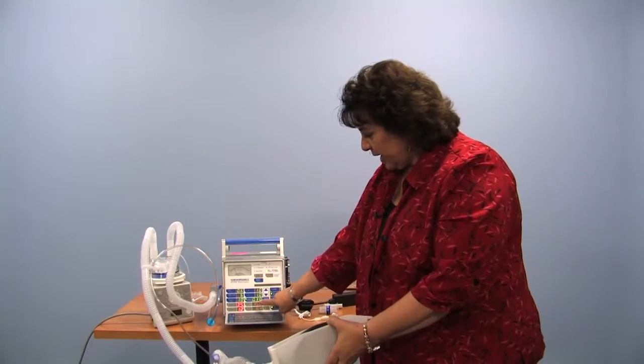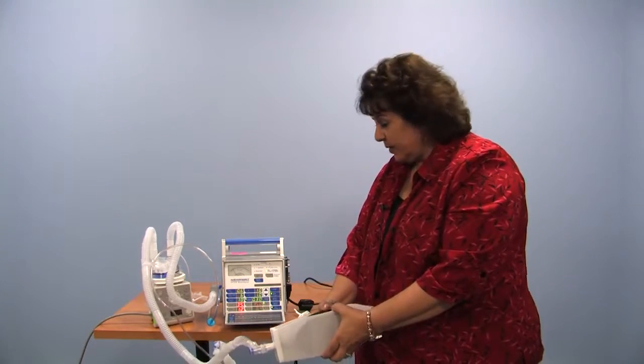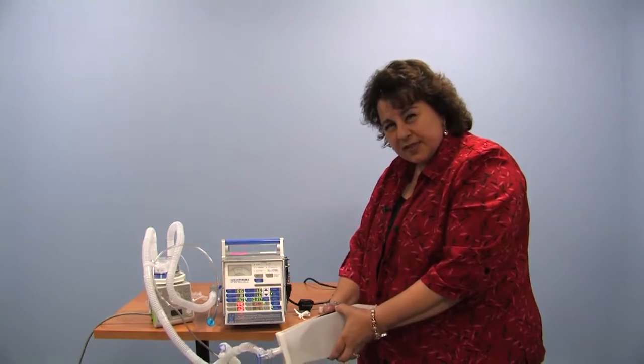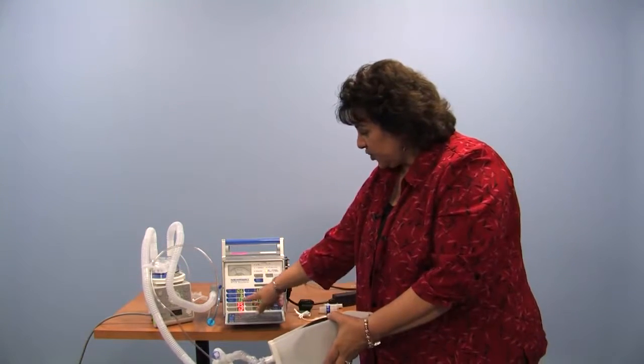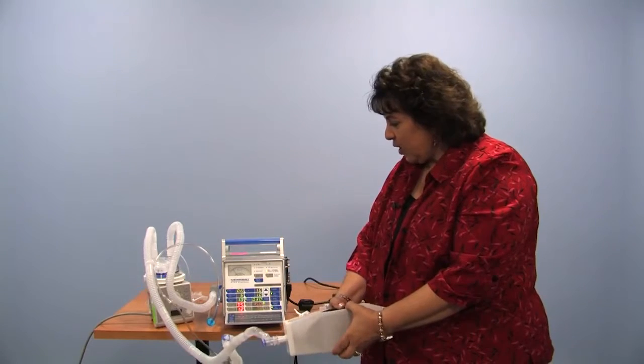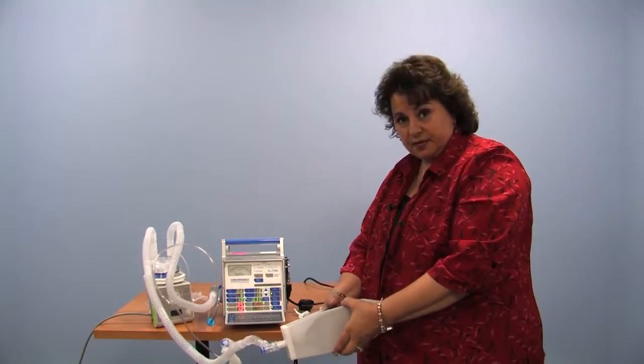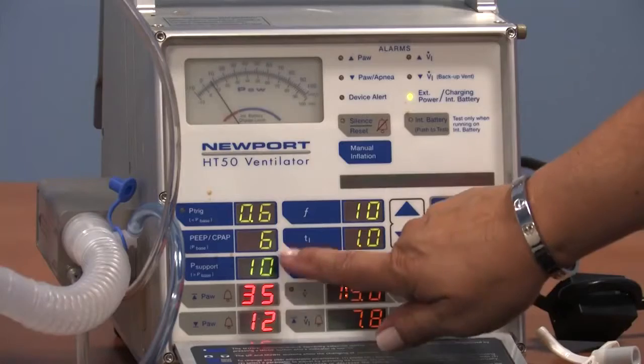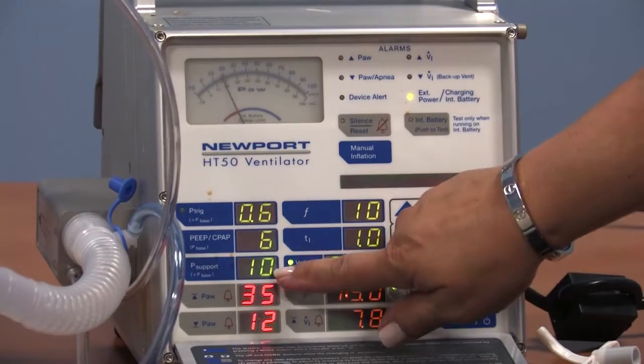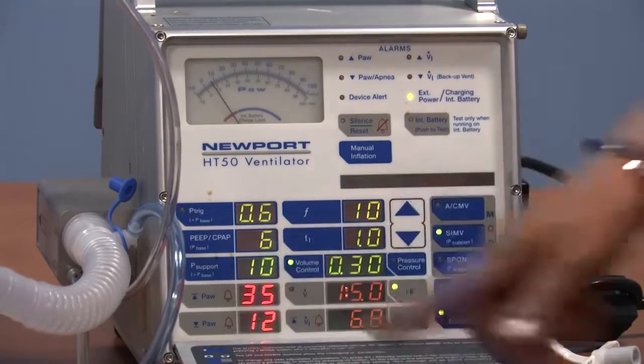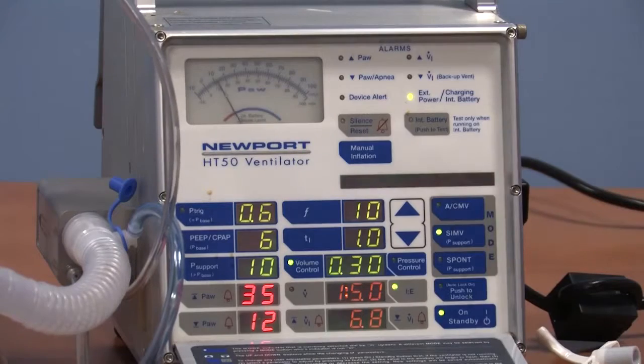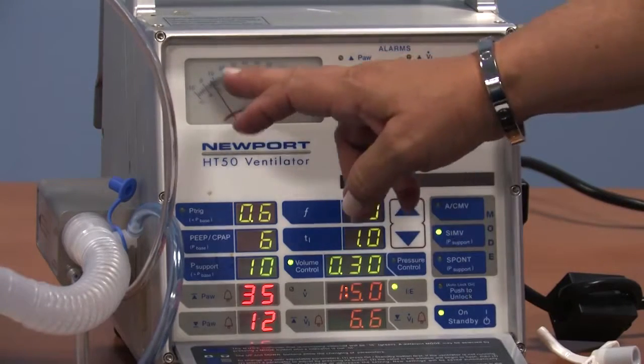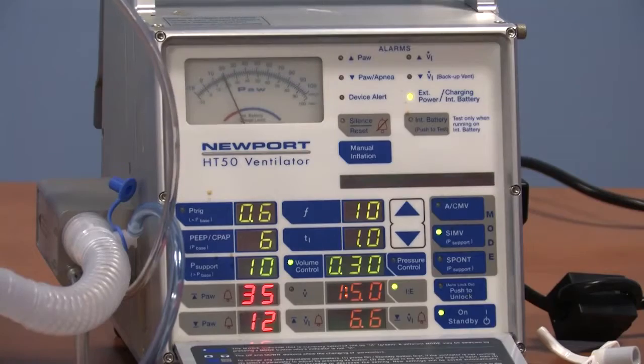Now I could be initiating one of the 10 breaths that delivers 300 cc's of air, and I could be initiating a pressure support breath. Well, how am I going to tell the difference? How are you going to tell the difference? Well, we know that this breath has been told, I want to give 10 of help over 6 of PEEP. That means the top number over here should be approximately 16 for that breath. And if we watch the needle, it should be going to about 16.